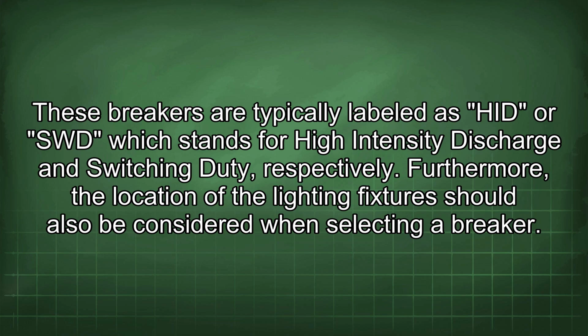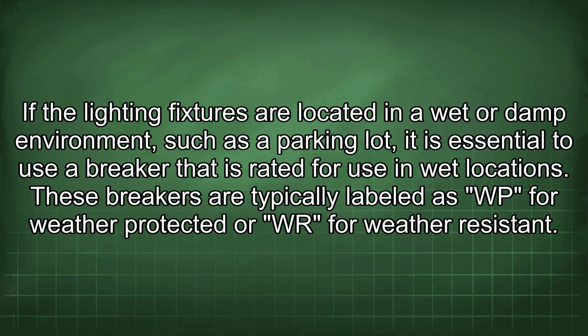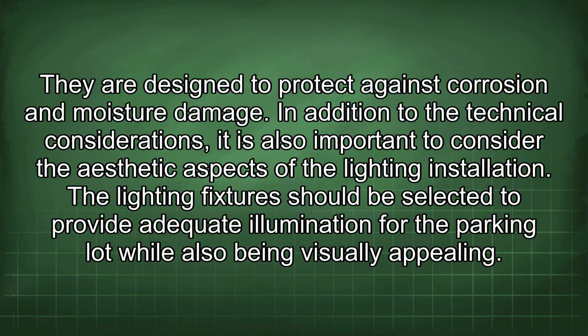Furthermore, the location of the lighting fixtures should also be considered when selecting a breaker. If the lighting fixtures are located in a wet or damp environment, such as a parking lot, it is essential to use a breaker that is rated for use in wet locations. These breakers are typically labeled as WP for weather protected or WR for weather resistant. They are designed to protect against corrosion and moisture damage.